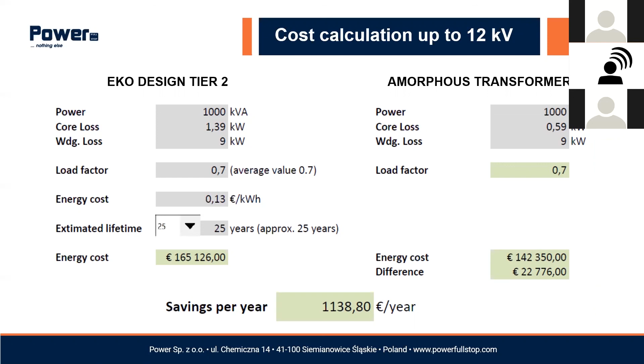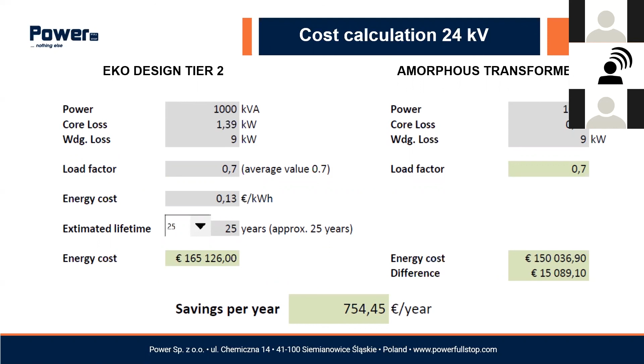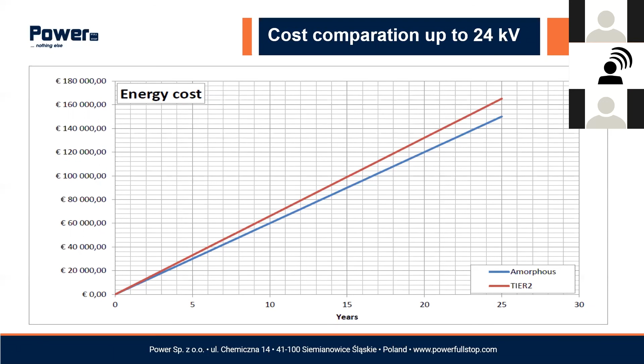Here we have the comparison for 1000 kVA, insulation class 24. And here the savings are lower. It's around 15,000 euro if we consider 25 years of operation time, around 754 euro per year. Now you have the answer why in Europe we do not use these transformers. They are quite expensive, and they still have some technical problems which have to be cleared, but they are really super efficient. And I'm quite sure they will be the future of the market.